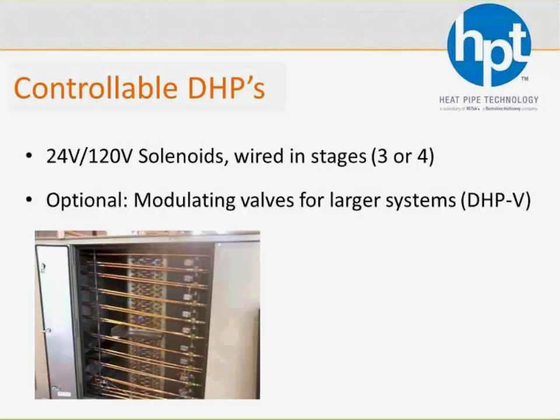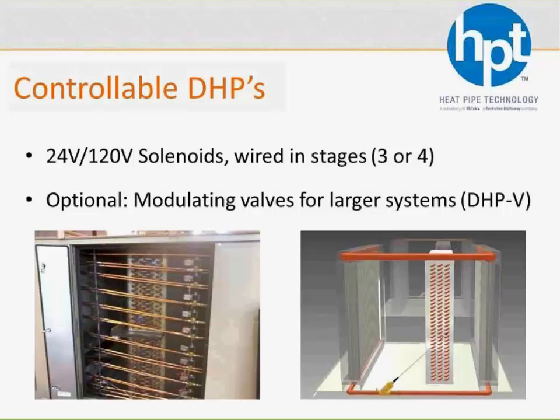Now, in larger systems where the number of solenoid valves just gets to be ridiculous, we can go to what we call our split passive type wraparound heat pipe, where we've got vertical tubes and common liquid and vapor headers going from pre-cool to reheat. This does allow us to simply use modulating valves in a liquid line, which is going to greatly reduce the number of valves. But it also diminishes performance.